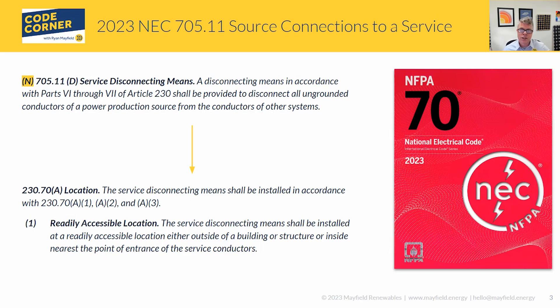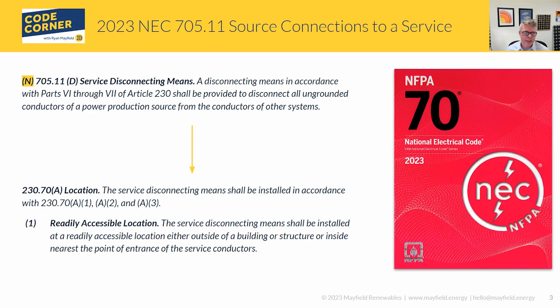Part 6 of Article 230 is service equipment disconnecting means. Reading through 230.70A, it talks about location: the disconnect needs to be in a readily accessible location, either outside the building or structure or inside at the nearest point of entrance for the service conductors. So what we're really left with is no code restriction on the length of those conductors. The disconnect just has to be in a readily accessible location and the overcurrent protection needs to be integral with or directly adjacent to that disconnect.